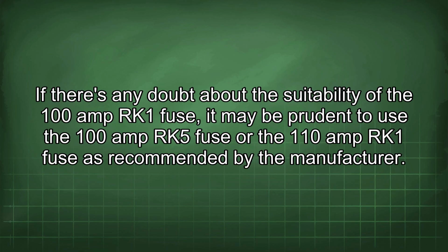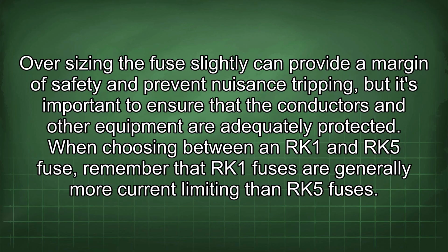If there's any doubt about the suitability of the 100 amp RK1 fuse, it may be prudent to use the 100 amp RK5 fuse or the 110 amp RK1 fuse as recommended by the manufacturer. Oversizing the fuse slightly can provide a margin of safety and prevent nuisance tripping, but it's important to ensure that the conductors and other equipment are adequately protected.